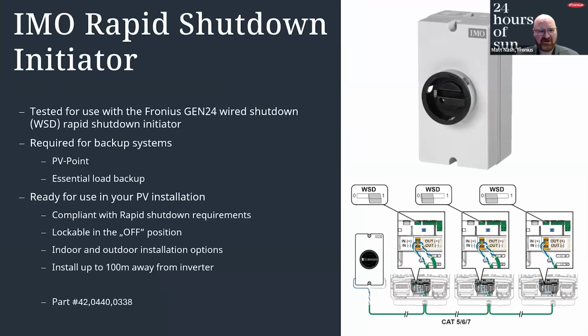And speaking of that rapid shutdown initiator, we have partnered with IMO for that. This will allow rapid shutdown in case of a grid outage, utilizing either the PV Point or the essential load backup. So you can wire these in and daisy chain up to 27 inverters to one switch. You should be able to just walk up to it, flip the switch, it initiates rapid shutdown, and this will get you to code compliance.